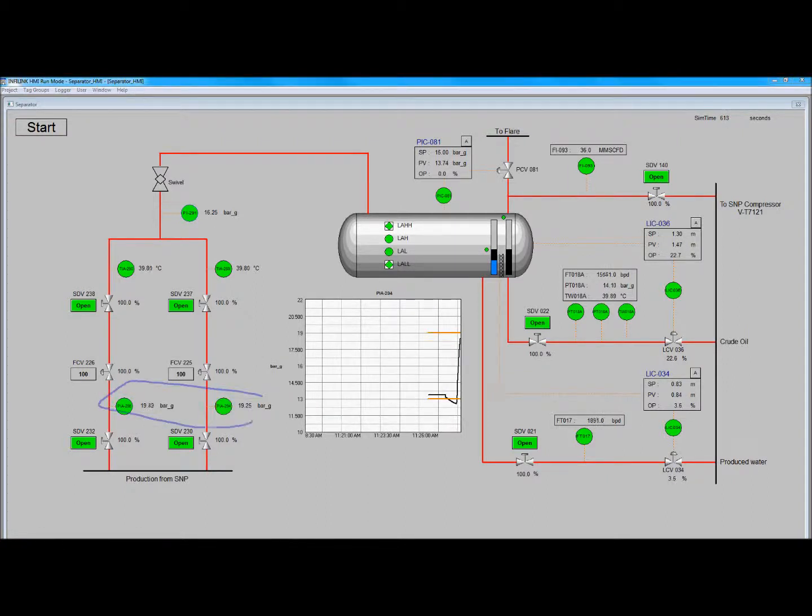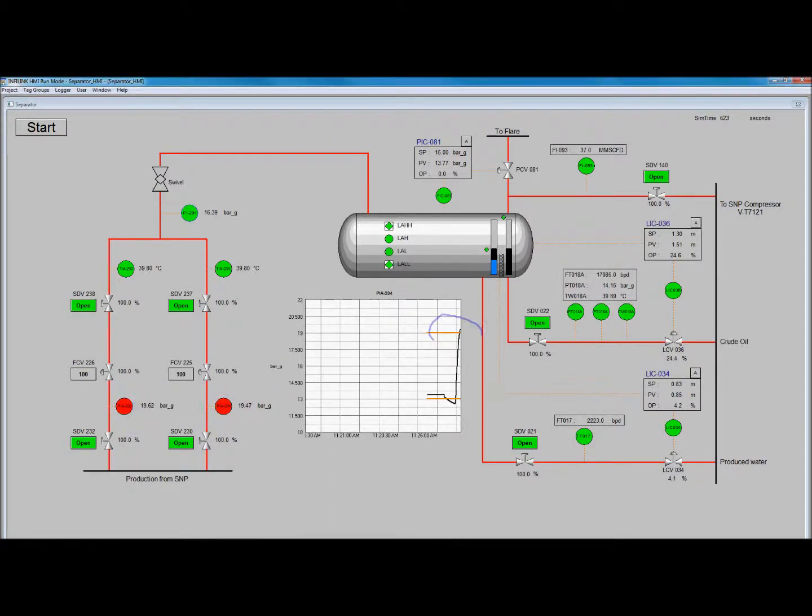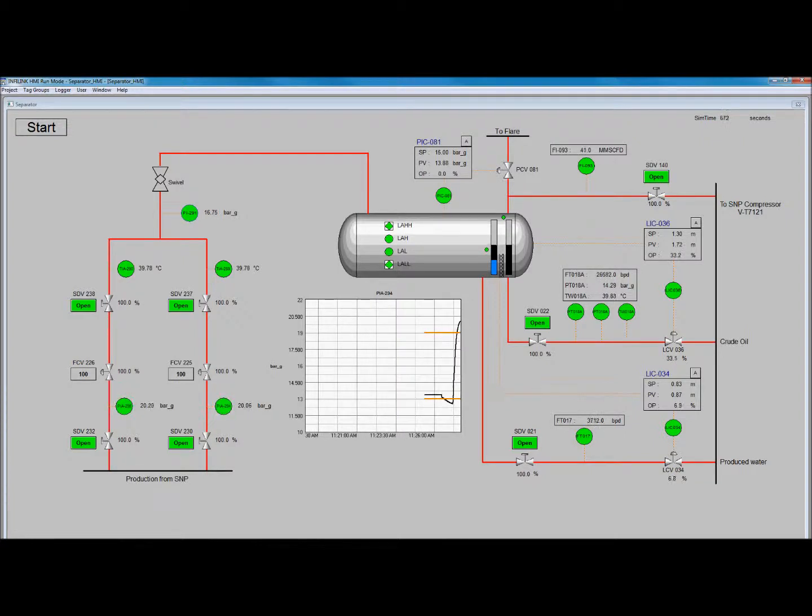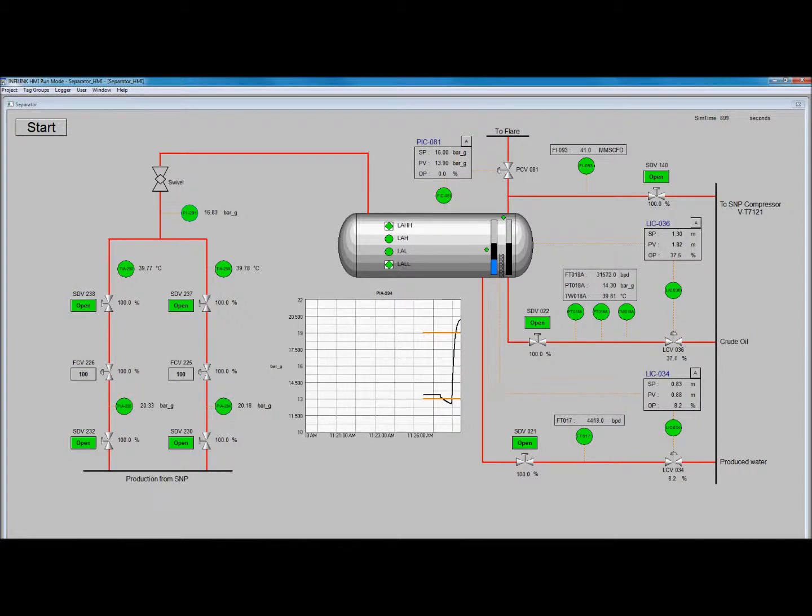Yes it does. The pressure reaches PAH. For now, let's just observe it. Maybe it will go away. It seems that the pressure is staying above PAH. In this case, the riser is rated for pressures above 100 bar, so that is not a concern.